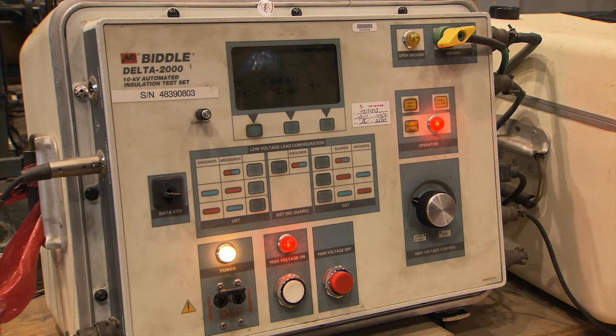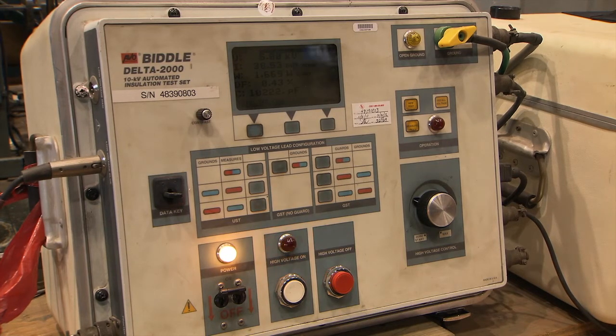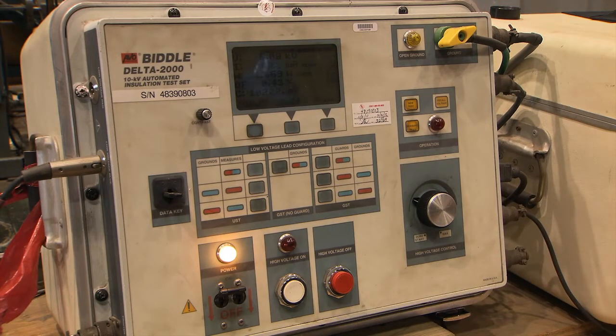The test is complete when a set of results appear in the display window and the red operation light goes out, followed by the red high voltage light indicating that the high voltage switch has shut off. Press the first button on the left under the digital display to print a copy of the test results. View the test results as they appear in the display window.